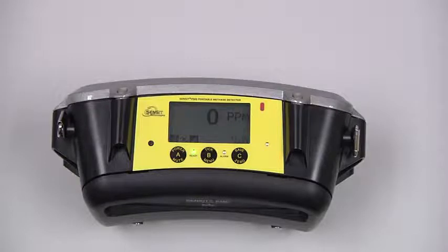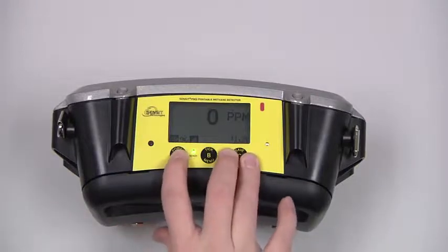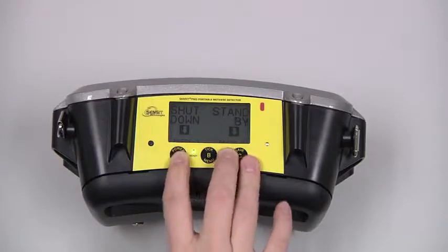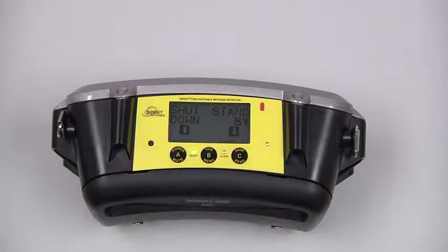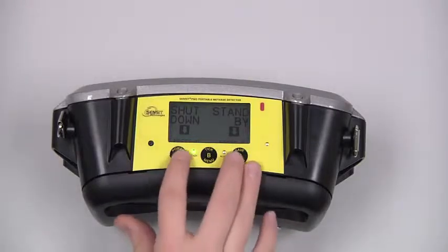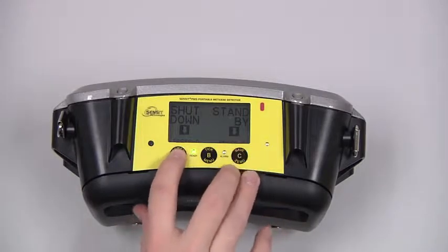After use, allow the instrument to clear out in a clean air environment, and we can then power down by pressing and holding the A button, and choosing between either standby, which is a low power state, with the C button, or shutting down by pressing and releasing the A button.